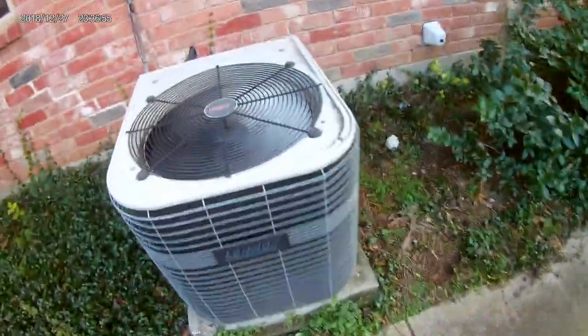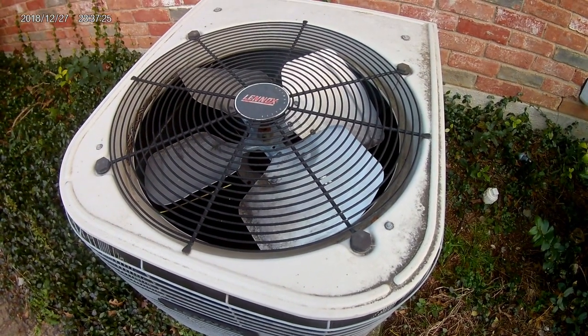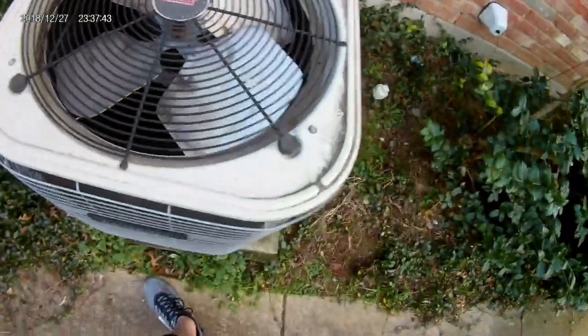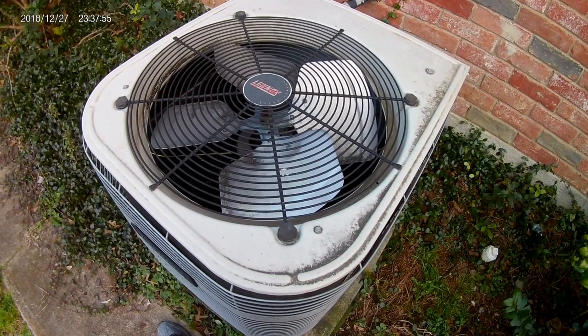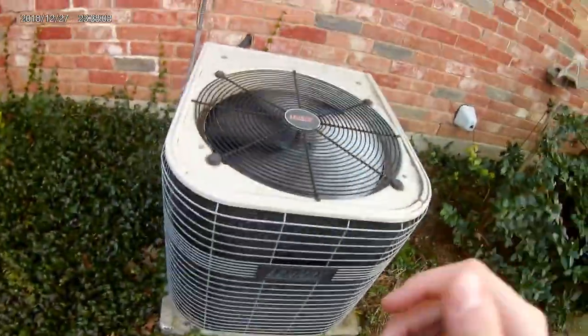Now all we're gonna do is just shut down. It just wanted to defrost. Caught it on camera — it's not very frozen, though. The refrigerant line's getting cold again. There it goes. That's really warm. Now it's cold. Wow — caught it defrost on cam.